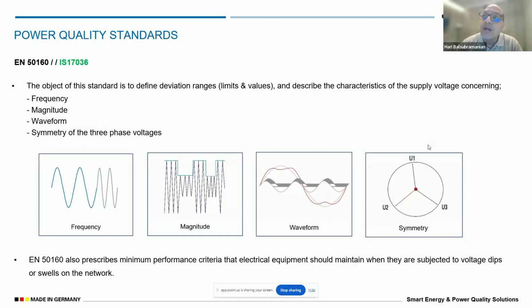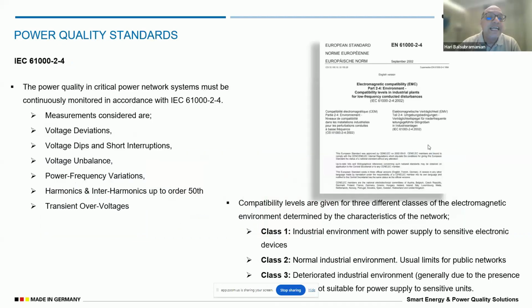It is measured over a period of 7 days' time. So usually EN 50160 is measured over a 7-day period. The frequency is measured every 10 seconds, and the magnitude, waveform and voltage are also measured every 10 seconds. And then there are different limits for each. For paucity of time, I'm giving only the headlines so that I can discuss more about IEEE 519. We can also discuss later, if you need more information, and I will be happy to share with you on EN 50160 and 61000-2-4.